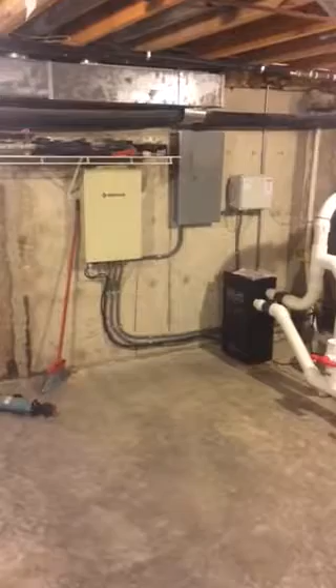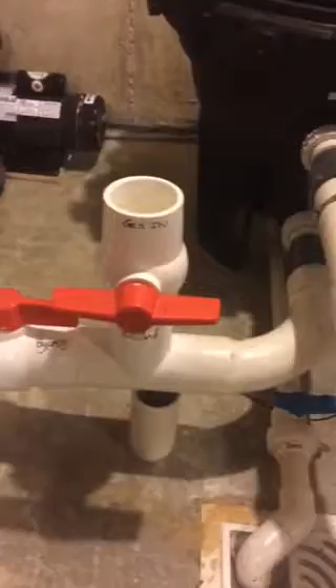This pump right here is the main system pump, and you see two lines. This is the in and out for our geothermal. It says geo in on this one, and geo out on the other. These are 3-inch lines. We need to go down to, I think it's 1.5 inch, or 1.25 inch lines that go in and out of these particular lines.